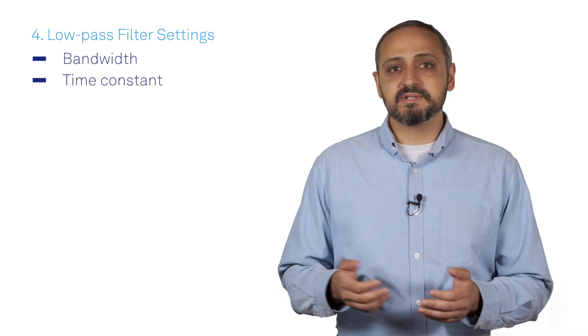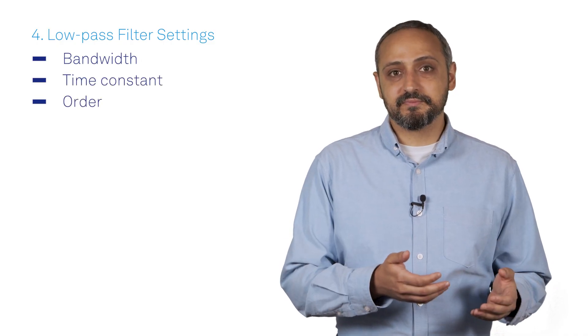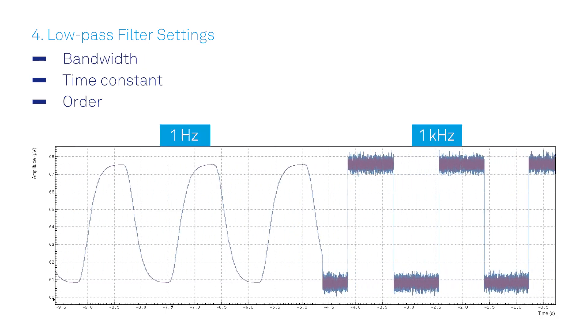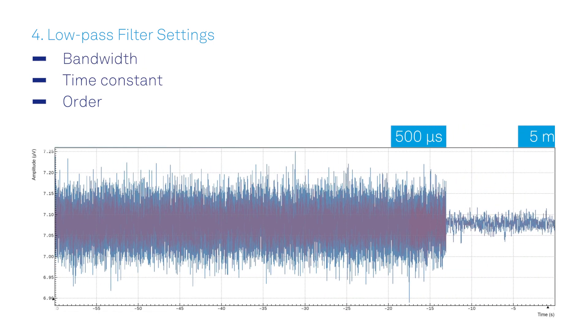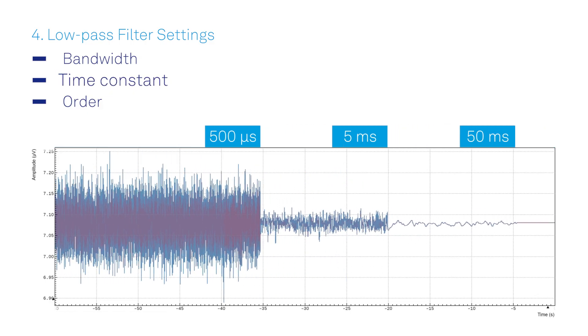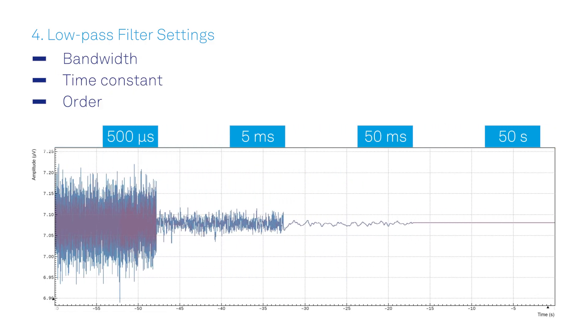Its specifications are the filter bandwidth or time constant and the filter order. Depending on your application, you might need a broad filter bandwidth with a short time constant for fast measurements, or a very narrow filter bandwidth to recover signals buried in the noise with time constants longer than a few seconds.